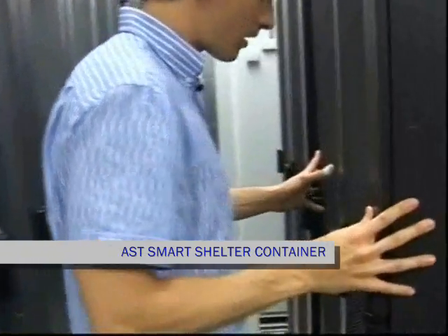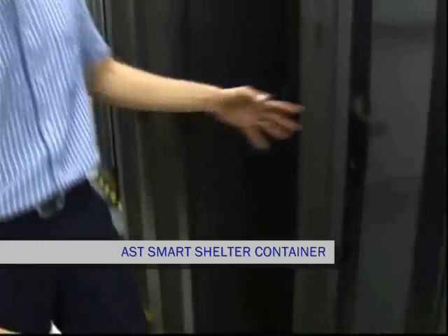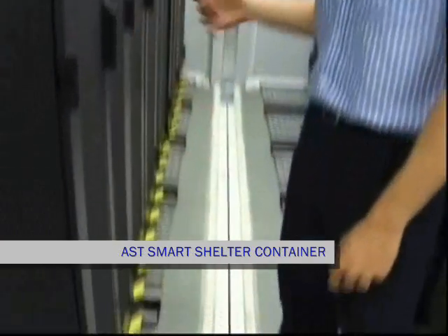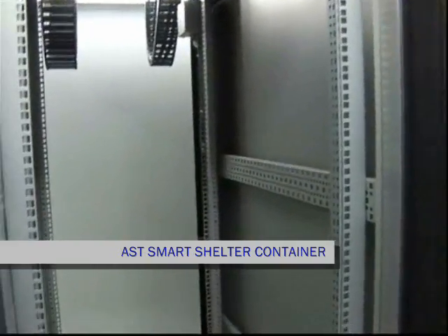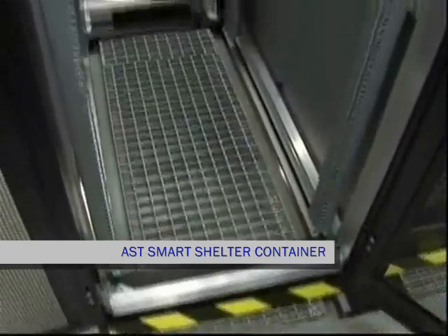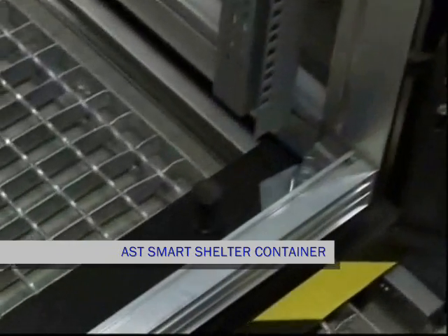If we take a deeper look at our rack design, even though these racks are standing without a railing system, as you see here, these racks can be moved back and forth, and we have enough space to provide easy and good maintenance of the racks. Nevertheless, in order to work properly inside a container with really tight spaces, we have designed a specific railing solution, capable of withstanding 1500 kilograms per rack, so you can assemble any manufactured rack, at any weight available on the market these days.